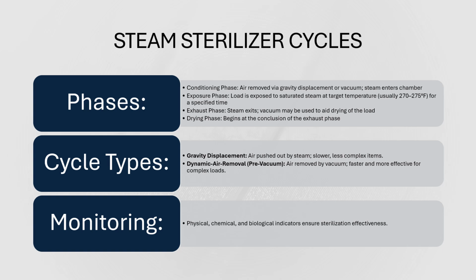This can be done using either a gravity displacement or a pre-vacuum. The next phase is your exposure phase. This is where the items are subjected to saturated steam at high temperatures for a specific period to ensure microbial destruction. The temperatures are usually between 270 and 275, depending on what the manufacturer says.